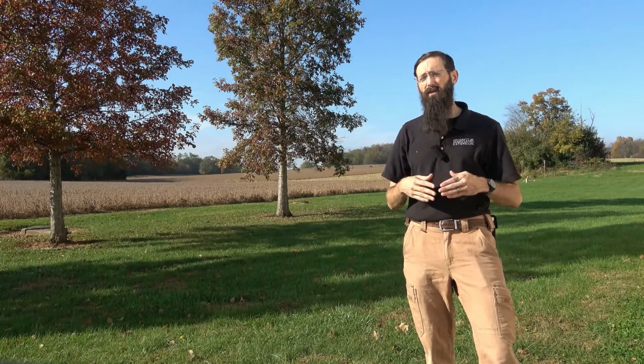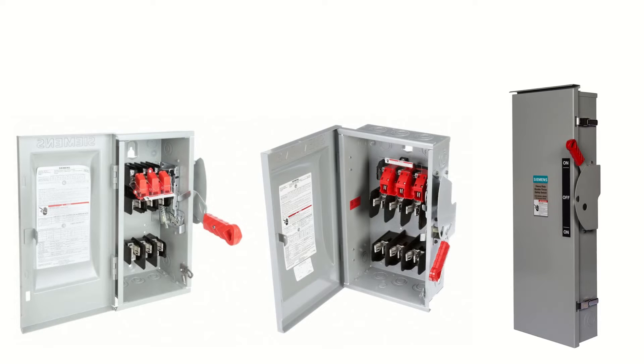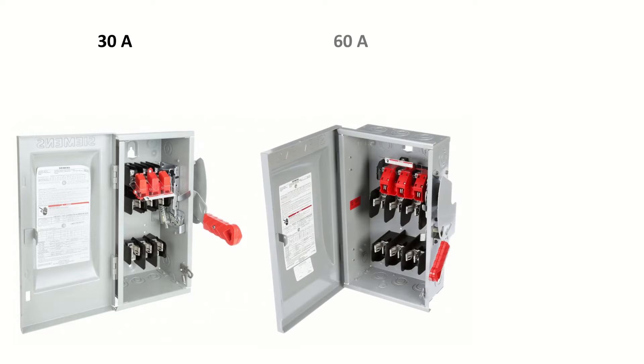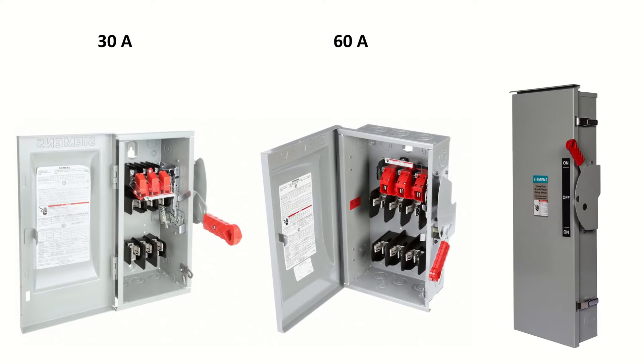Now that we've discussed these two options, we'll consider how to size and select appropriate disconnect switches for your system. Disconnects come in a number of different sizes or amperages, typically ranging from 30 to 800 amps. Most residential projects will deal with the 30 to 60 amp range, while larger consumption levels in multi-inverter situations will often deal with 100 amps or higher. Proper planning is necessary to determine the appropriate size for your system, which will be based on the size and power output of your PV system.